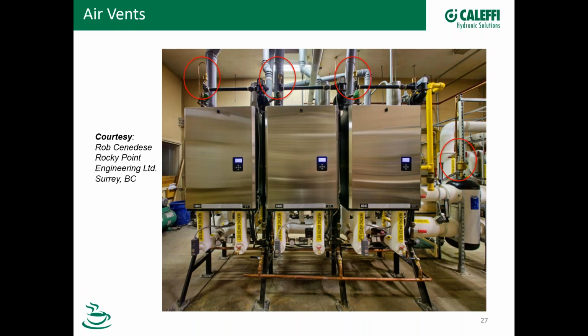Moving on, this is a great picture. I like this for a couple of different reasons. Here are 3 boilers installed. Now up above, I know it's hard to see, but you can see the air vents in these little red circles, but what's on top of those is a piece of copper tubing. Now what this contractor has done is put a discharge tube on top of these air vents, and we make a little adapter that you can screw on where the vent cap goes, and it takes you to a 1/4 inch NPT. So from there you can put a compression fitting or some kind of a discharge tube. That's in case these air vents do get a little debris or get clogged up for any reason, and they start to spit water, then you won't drip on top of the boiler and cause any damage.